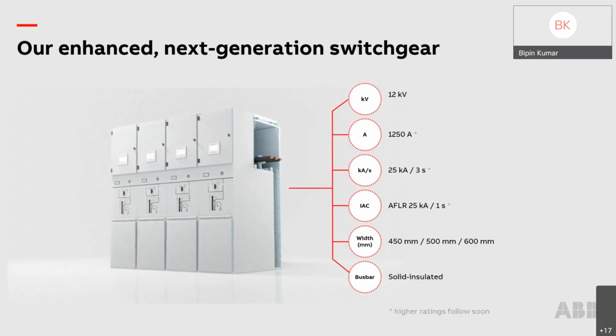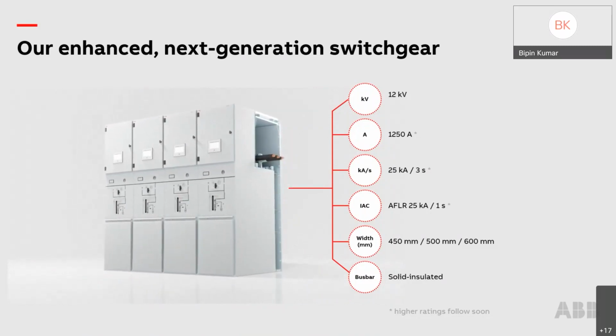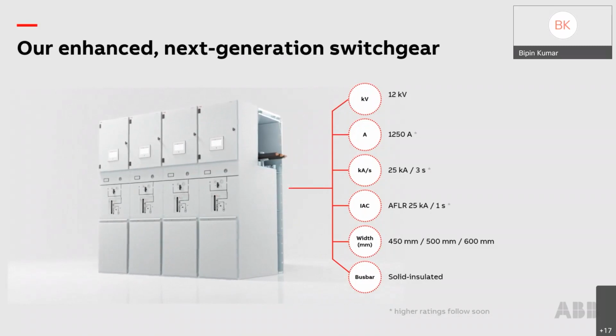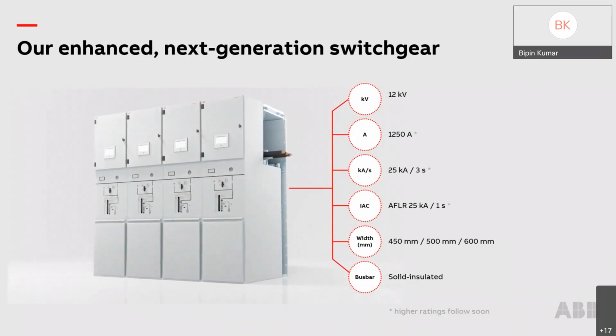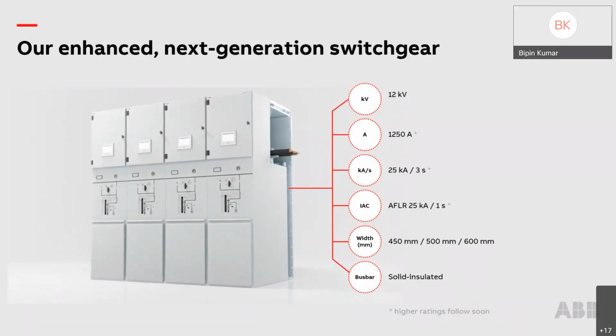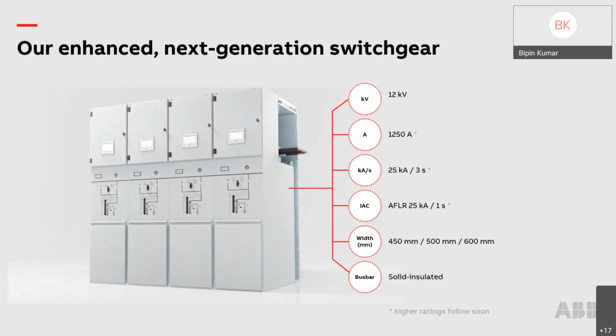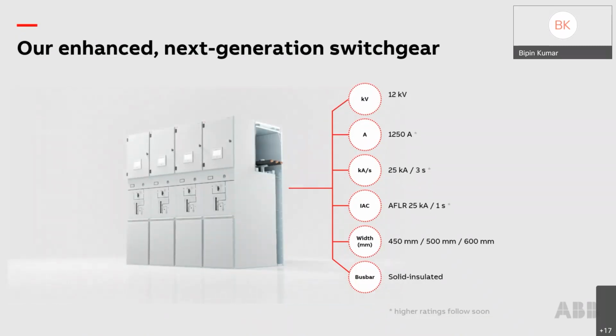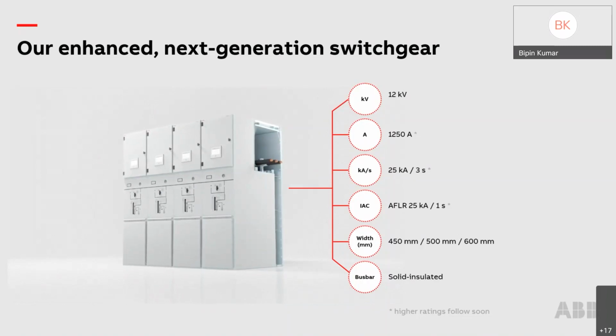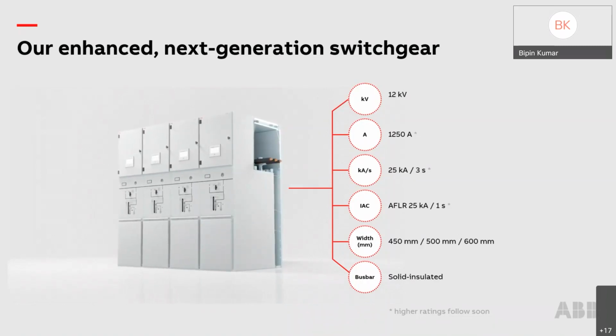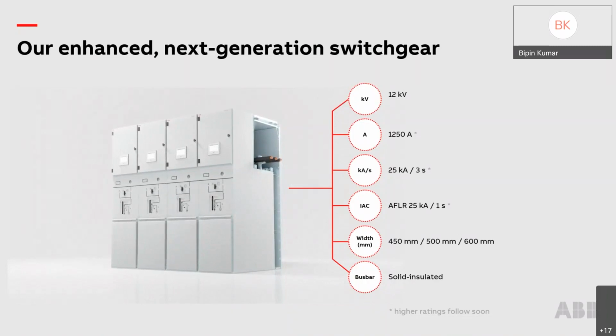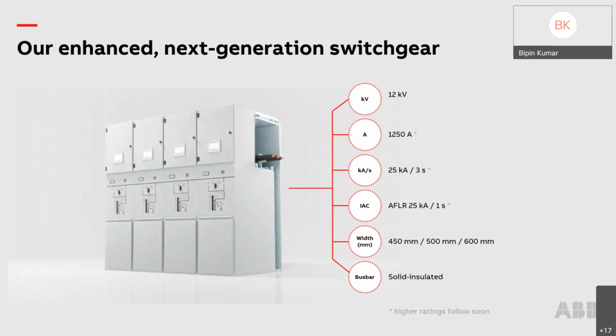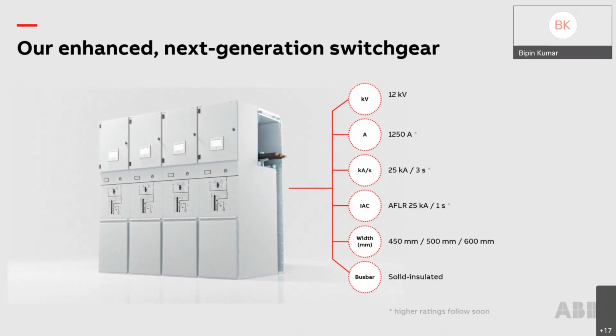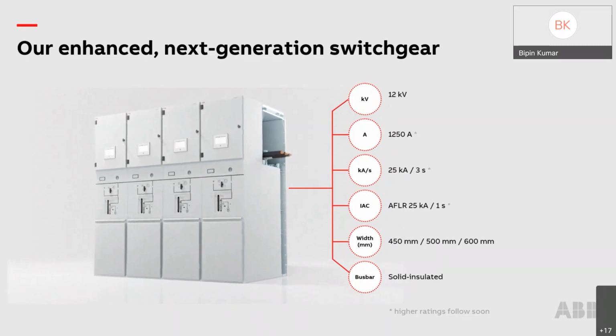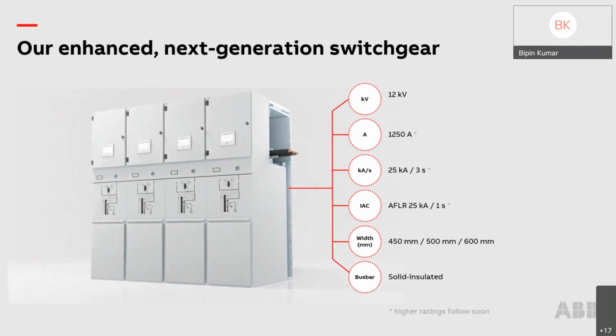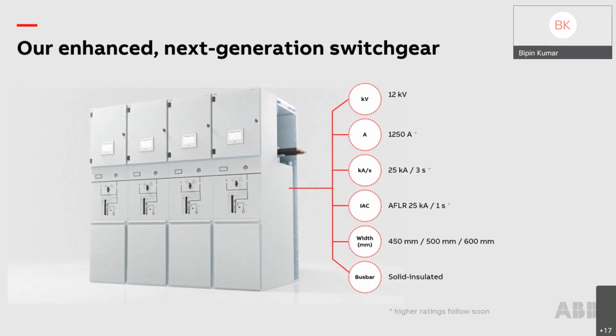And this particular product, what you are seeing, is a step in that direction. ABB has been able to develop a gas insulated switchgear which is able to work with SF6 and also with dry air. So this is a product which can interchange the insulating medium either right at the start when one buys it, or during the service time of a switchgear. Changing the insulating gas does not change the service life of a switchgear. So if it was 40 years earlier, it would continue to be that way.